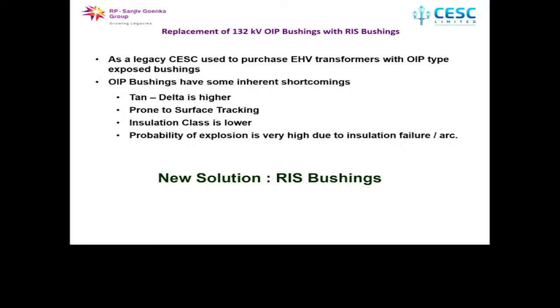Our network is in a city area, so it's congested. There are some inherent problems in these OIP bushings. Tan delta tends to be higher, and we often have problems, especially in the rainy season, or the first rain after a long dry season, with tracking along the surface of the bushings.